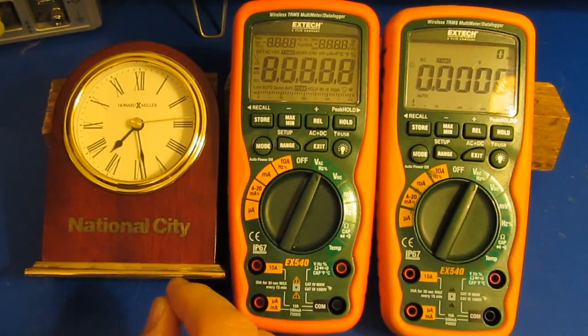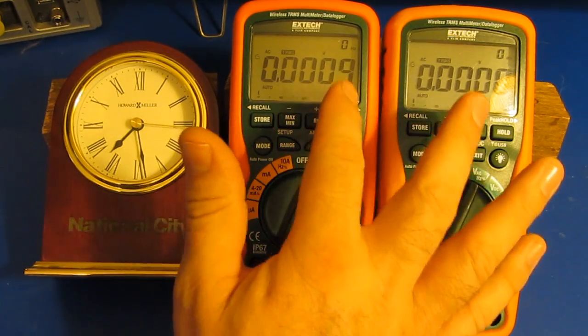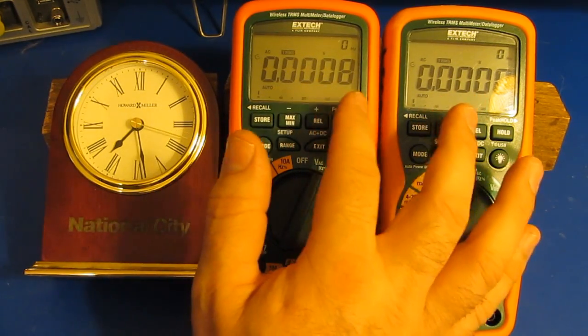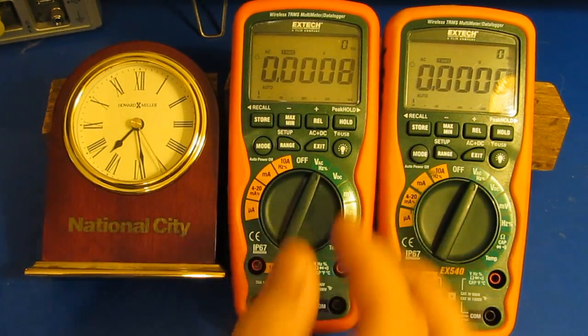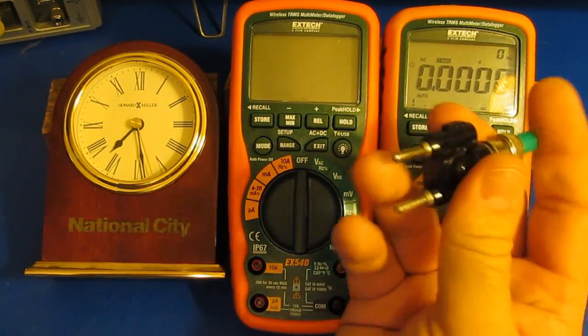This meter on the other hand, you can see it will read about one millivolt. And so it's .82, I've seen it as high as about 1.1 millivolt. That really has nothing to do with the input leads.